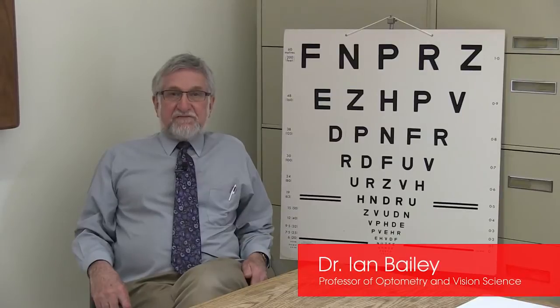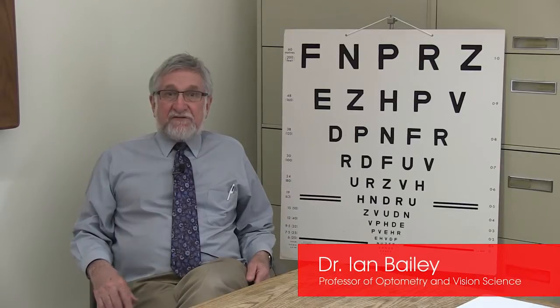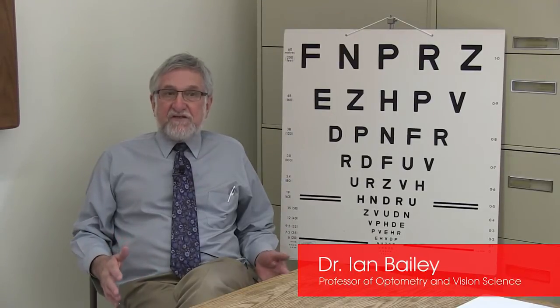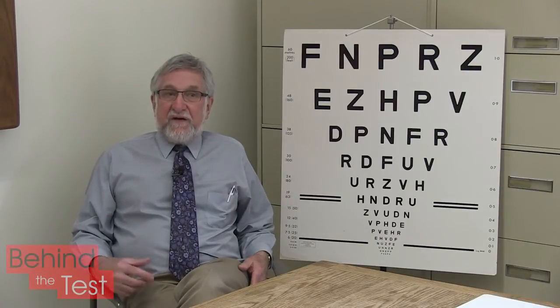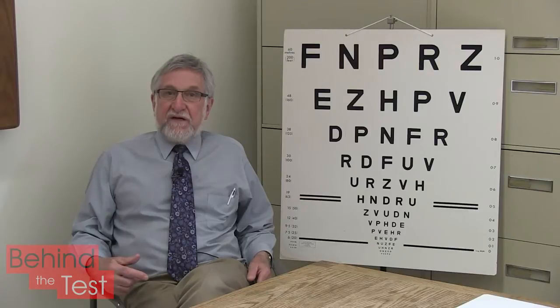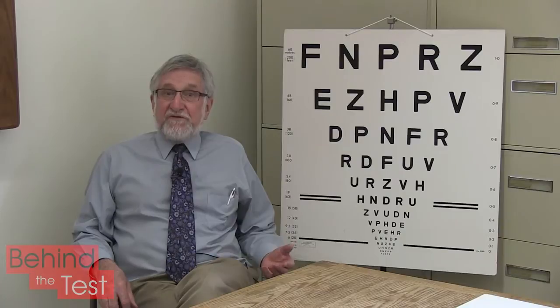The Bailey-Lovie test is really a set of chart design principles that lay down the rules for measuring visual acuity. The important thing about the Bailey-Lovie design principles is that the visual task is the same at each size level. As you go from one size level to the next, it always represents the same amount of change in vision — whether you're at the top of the chart with very poor vision or near the bottom with good vision, each step always carries the same meaning.